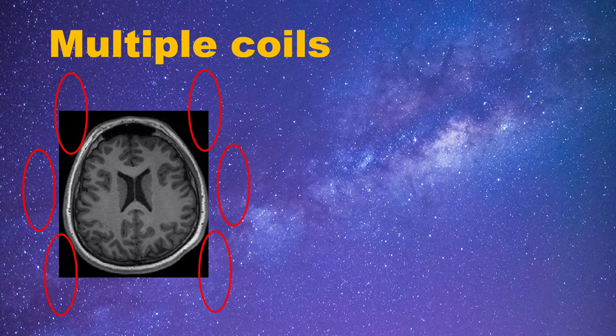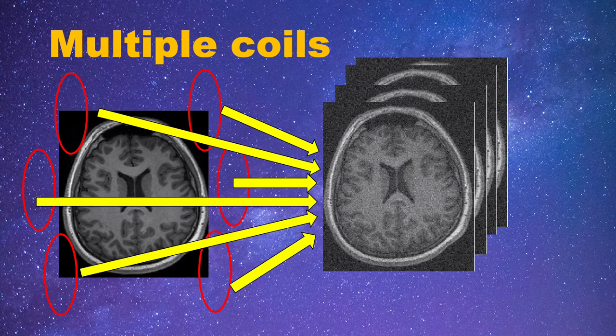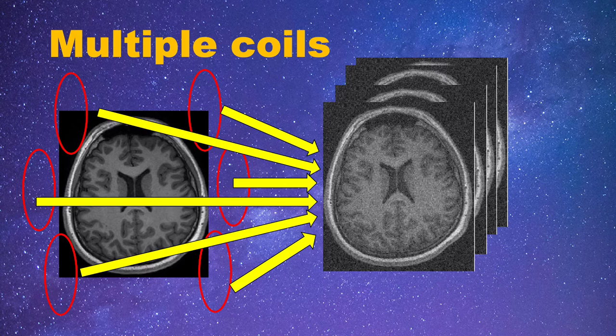Here, with the help of those combined multiple coils, we can get multiple images at the same time. Their combination can improve the SNR of the image by a lot. This is actually the original motivation of building such multi-channel receiver coils.